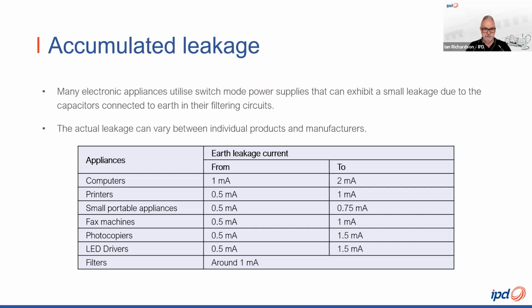And in this particular store, they were having tripping of RCBOs on the lighting circuits. So naturally, we were called in as the product supplier to come in and investigate. And once we started looking at it, we said, no, this just smells of accumulated leakage. And the consultant was there saying to us, no, can't be, because all the stores are the same. This is the only one where we have the problem. So we did some further investigation.